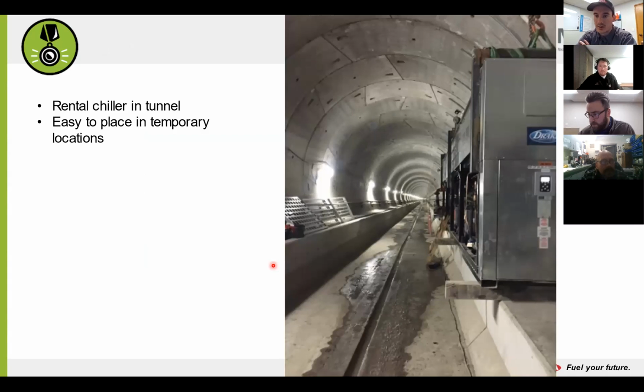Here's a picture of a chiller that is a rental chiller. They brought it in on a truck, dropped it, and they were using this. It was purpose built. Seth, if you wanted to talk to this, this was for the tunnel where they were trying to freeze the soil, right? When they were doing drilling. That was for Sound Transit up by UW, that tunnel they dug. They bored the tunnel, they lined the tunnel, and then they used it to freeze the ground in the middle of the tunnel. So they bored holes and put heat exchangers in a kind of horseshoe shape, froze the earth, and then they dug the earth out to make the escape tunnels for people to get out in emergencies.